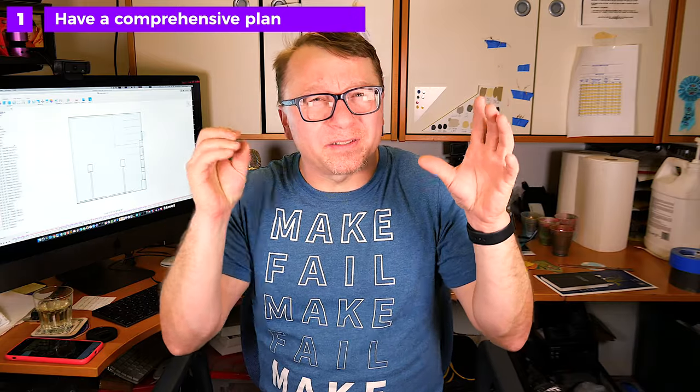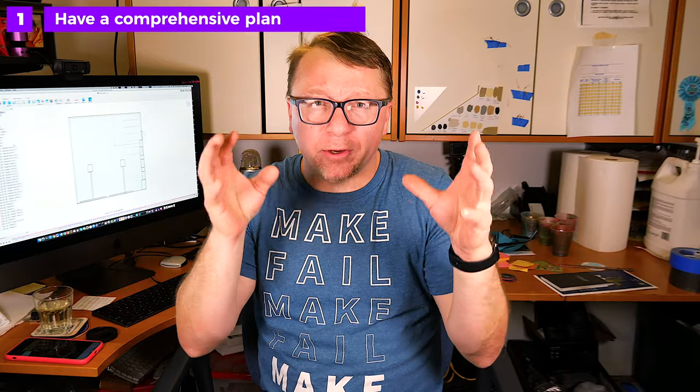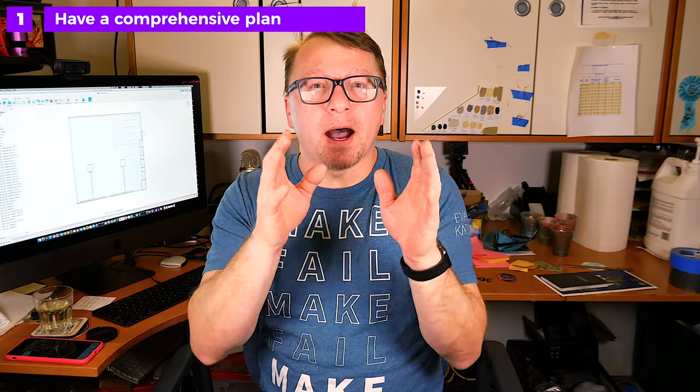Lesson learned number one: start with a plan and make it as complete and accurate as you can possibly make it. I actually started by modeling my garage in Fusion 360 and put all the artifacts that are already in the garage that I can't move into the plan, and then worked my conduit, my boxes, and all of my connections around what was already there. It was tremendously helpful to go into Fusion and do a quick model, and then I could play around with different options putting receptacles and conduit in certain locations. Let's go ahead and switch over to Fusion and I'll show you what I've done.